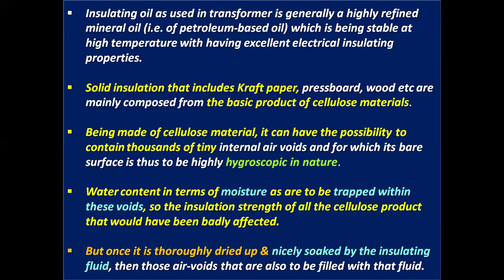Insulating oil as used in a transformer is generally a highly refined mineral oil, that is, petroleum based oil, which is stable at high temperature with excellent electrical insulating properties. Solid insulation that includes kraft paper, pressboard, wood, etc. is mainly composed of basic cellulose materials. Being made of cellulose material, it can contain thousands of tiny internal air voids, and its bare surface is thus highly hygroscopic in nature.